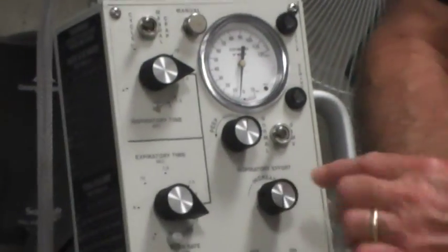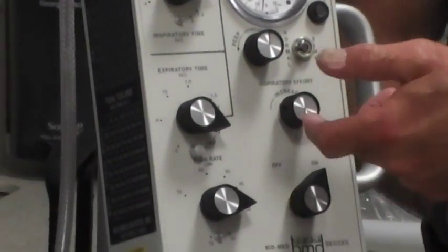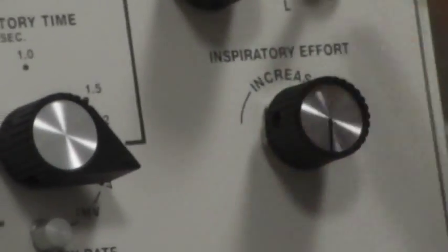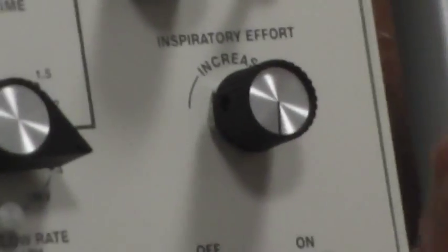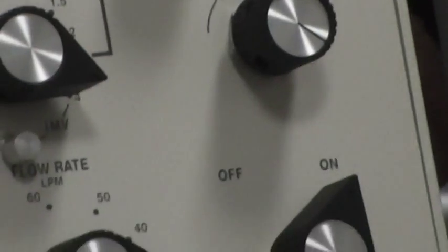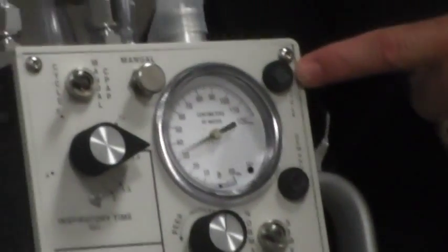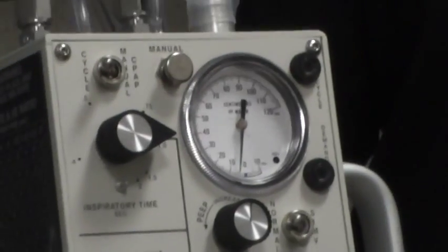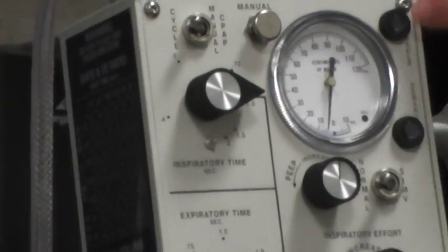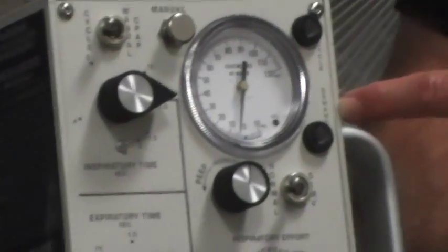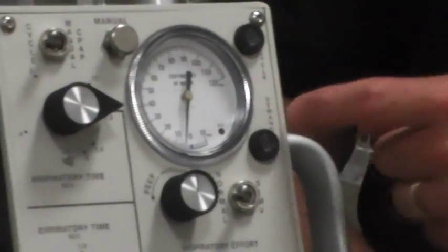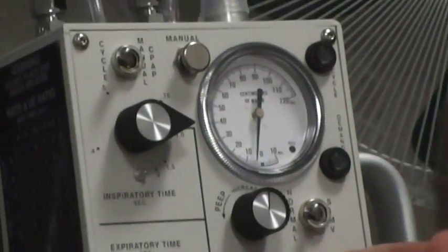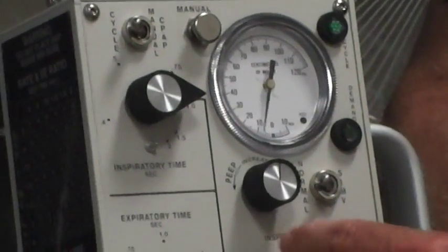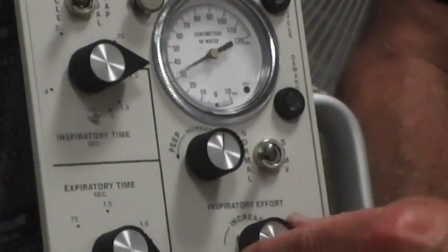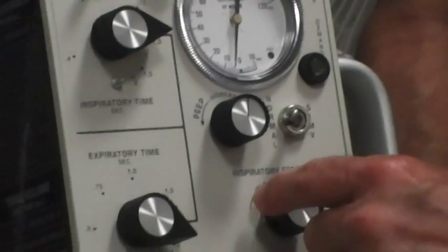Inspiratory effort seems kind of backwards: increasing is this way, so if I want the patient to trigger, I want to decrease my effort. If you look here, see this little indicator that's showing every time the vent cycles? It's not a light, but it's a pneumatic signal. Demand would be the patient actually triggering. So what you do is you decrease the effort until it auto cycles, and then you back it up about a half a turn.